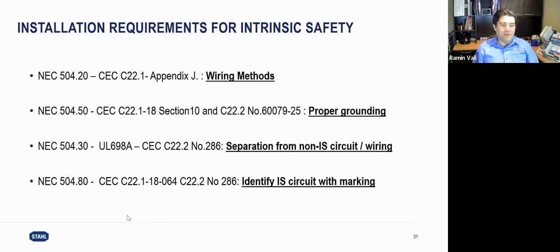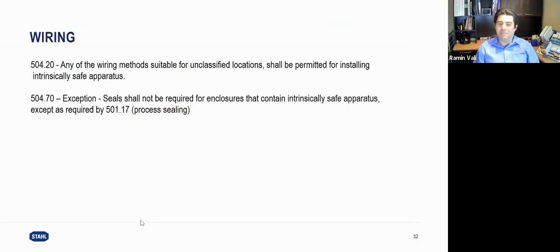Well, I like that the slide presented by Barbara is about the installation matters. That means I never forget that I need to look at the control drawing. And that control drawing is always the best reference for us to start. But in addition to that, there are some other codes that we have to observe when we are using an intrinsically safe loop. Four of these codes are summarized here: wiring method, grounding, separation of non-IS and IS wiring, and of course, identifying IS circuits.